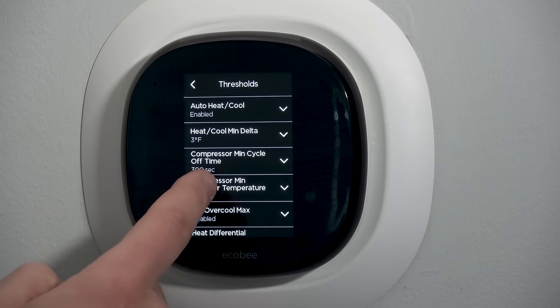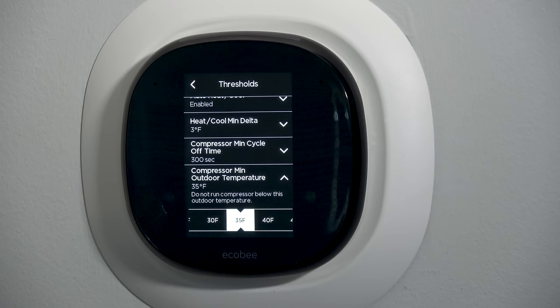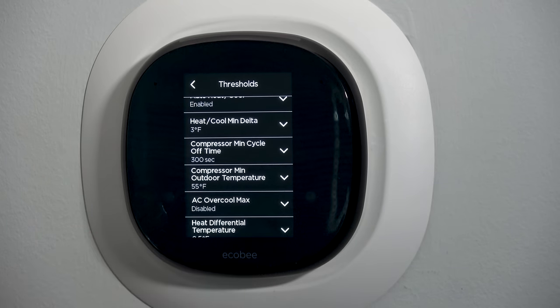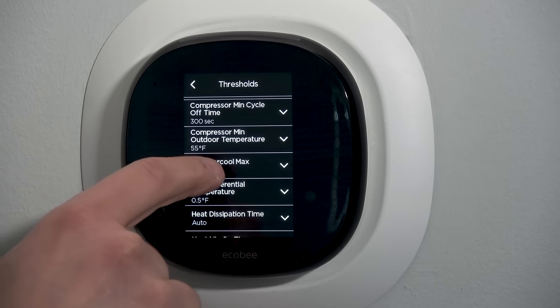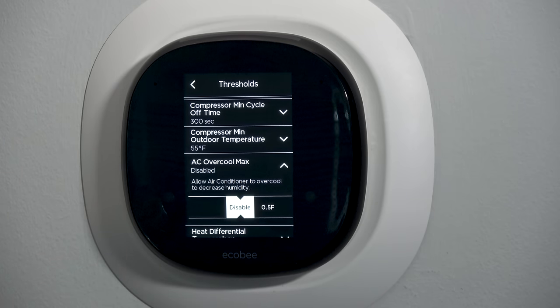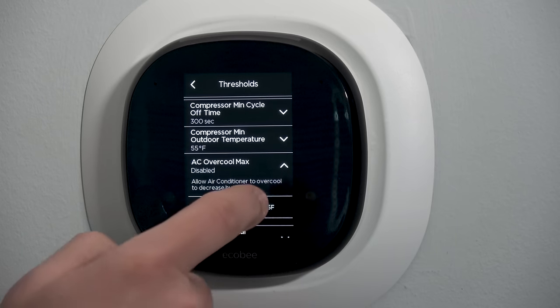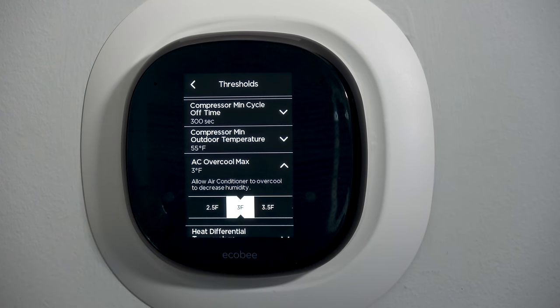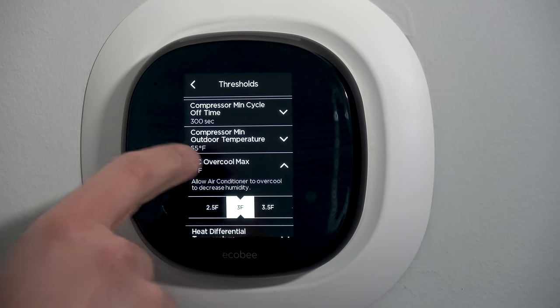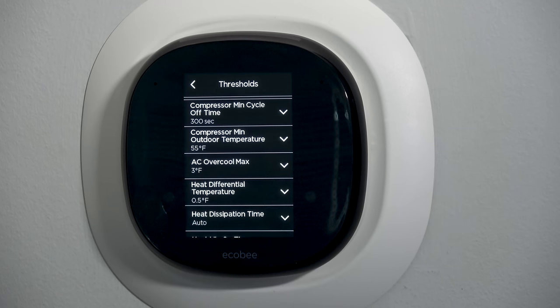Compressor minimum outdoor temperature: the coldest temperature you want to run the compressor — do not run it below this. If you want to say below 55 degrees there's no reason to run this compressor and disable cooling completely, you could do that. AC overcool maximum is currently disabled. If you're in dehumidification mode, this is the maximum amount the stat will allow the system to over-cool. A common setup is a 78 degree set point allowing overcooling by up to 3 degrees — I highly recommend you turn this feature on with 3 degrees as a good setting.